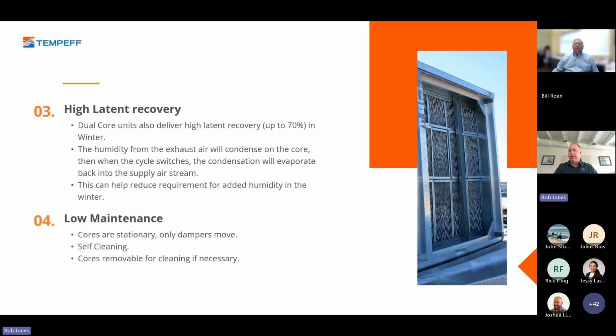There are two things people will not complain about in the wintertime. When you're bringing in outdoor air, they never complain that it smells too fresh in the building. And when you're bringing in latent recovery, they never complain that their skin feels good in the winter. We have low maintenance. Our cores are stationary, only our dampers move. They're self-cleaning, and if necessary, such as a casino application where smoking is allowed, our cores can be easily pulled out, no bolts or screws, hit with a pressure washer, cleaned up, dried off, and inserted back in, complete.